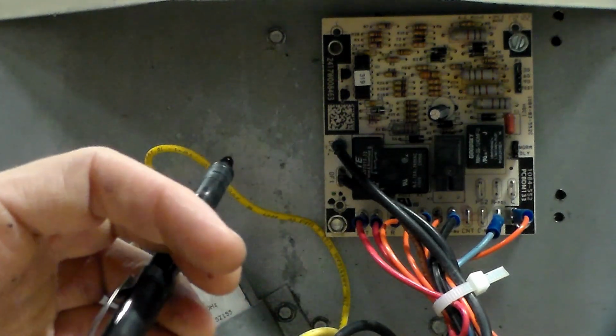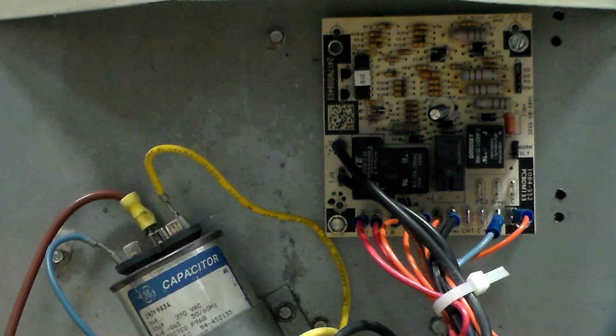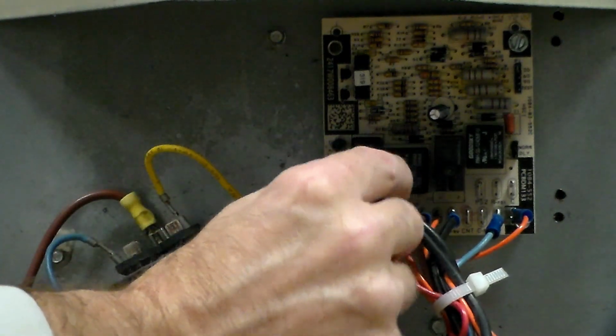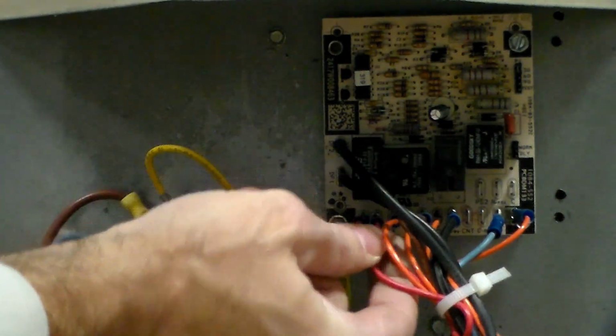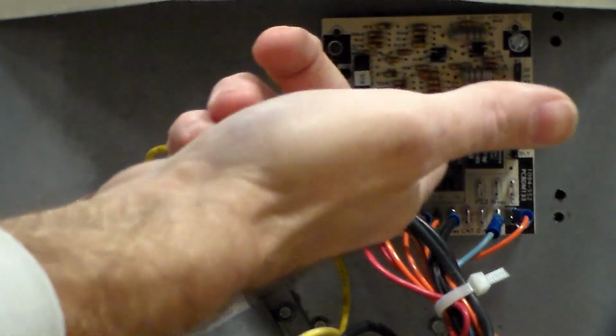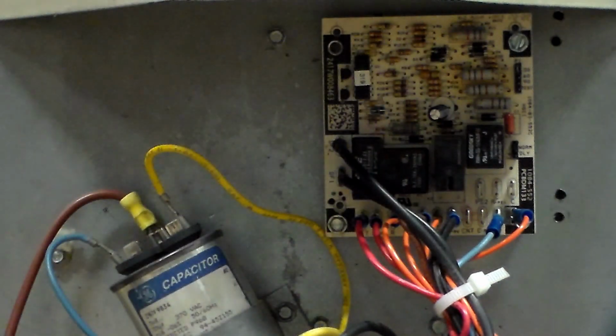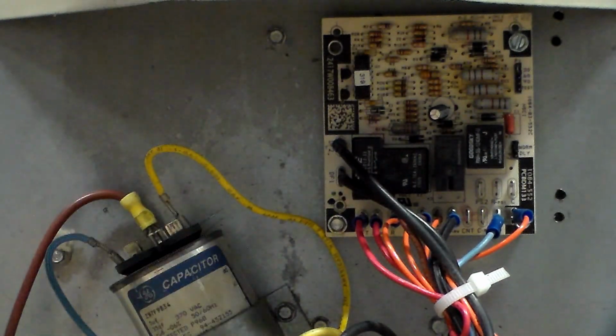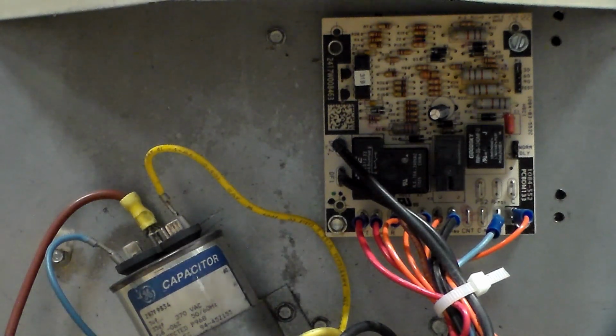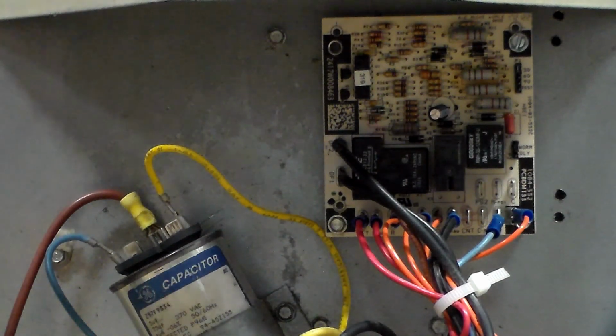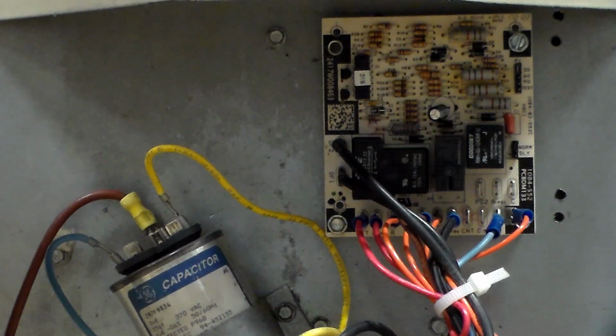You're always going to have your W, you're going to have R, O, C, and then you're going to have some kind of way to turn off that condenser fan, and you've got to have some kind of defrost termination sensor. You may or may not have a low pressure switch hooked up. In this case, we didn't need to have one. And usually if it has it on the board, you're going to have that pressure sensor. I don't really want to get into how to test those right now. I'm focusing on boards for this.